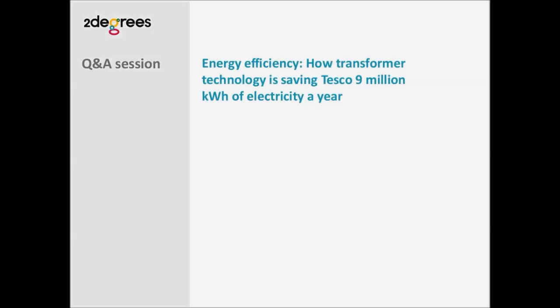The gains from this family of technologies are certainly not there, as they are with, for instance, an old magnetic ballast light fitting. But your modern high-frequency light fittings and LED light fittings are less susceptible, if you like. And then, yes, of course, there are certain voltage-dependent light fittings that may start to suffer when you start to drop the voltage down, traditionally starting to get below around 216 volts. More and more of those old light fittings will perhaps fail to strike somewhere between that down towards 210 volts. That's why it's generally good practice to try and maintain a voltage at load-bearing equipment of not less than 217 volts. Great, thanks, Steve.